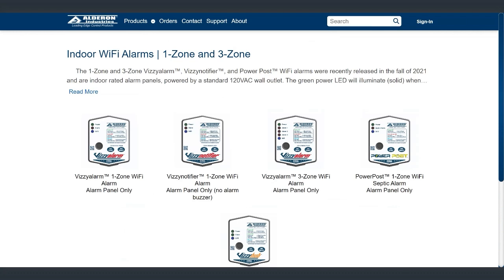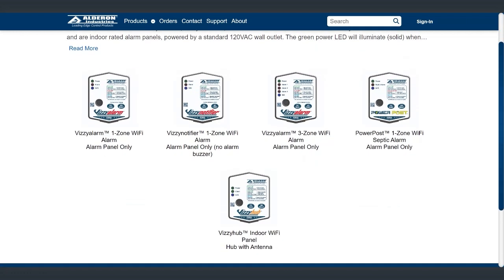And then of course all your other sensors, normally float switches. Then we have one specifically for our Power Post platform that just has a different label. It's basically the same thing as our Vizzyalarm, 1-zone on the left with a different label. It just tells the customer that it's a septic alarm because Power Post is designed for septic. And then we also have our Vizzyhub indoor Wi-Fi panel. So the Vizzyhub is used if you have a panel that has either cellular or Zigbee that can transmit out in the field up to 1,000 feet away, and then you have a hub inside your building that communicates with the Wi-Fi.